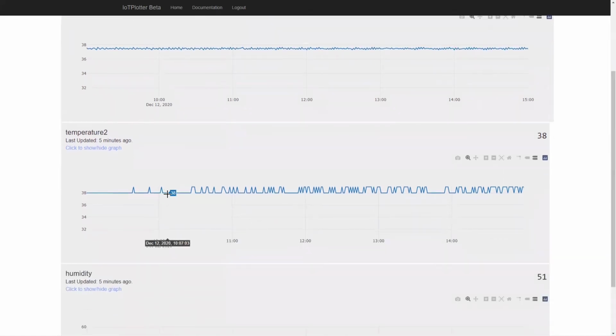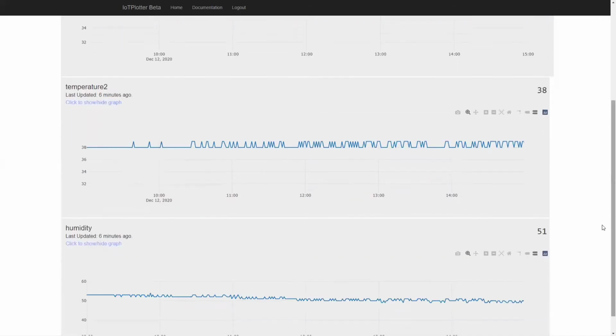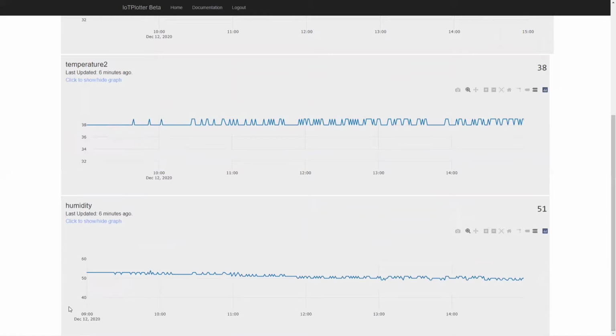This is the second temperature sensor that is within the humidifier itself. This is not as accurate as the first one. So here we see fairly big steps. This is 38 degrees and this is 39 degrees. And this is not as accurate as the other one. But nevertheless, we can see an average temperature of about 38 degrees here. Here we see the humidity. The humidity is not constant. This is measuring the relative humidity. So the relative humidity goes from 53 down to about 49.